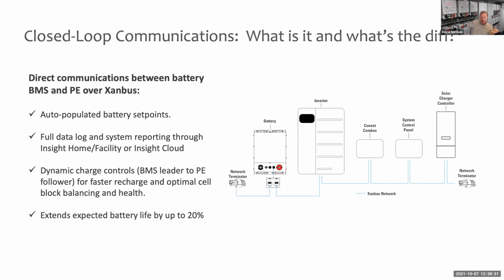If you were to have multiples of our battery on that network, we would be ganging those together on the other CAN channel that's native to the BMS, and that's called AE-bus. It's our proprietary CAN network that allows you to combine batteries into a singular operating block up to 20 nodes at a time. So we can have up to 140 kilowatt hours of our batteries combined on AE-bus, and then take an extension from that, denoting any one of those batteries to be a Xanbus battery, and all those batteries would collaborate and be broadcast over the Xanbus network.